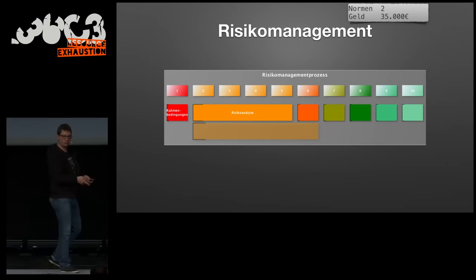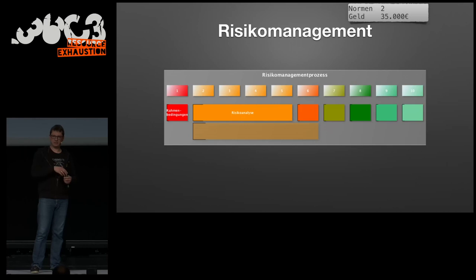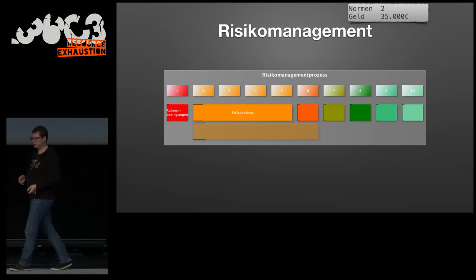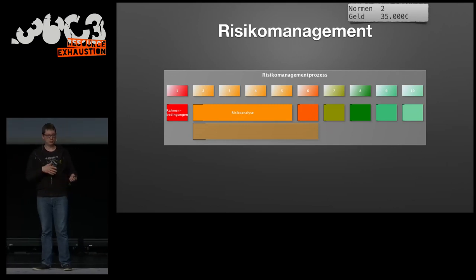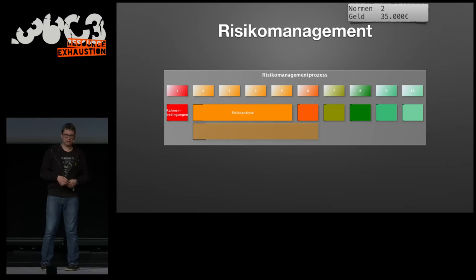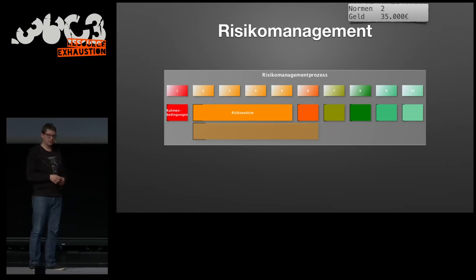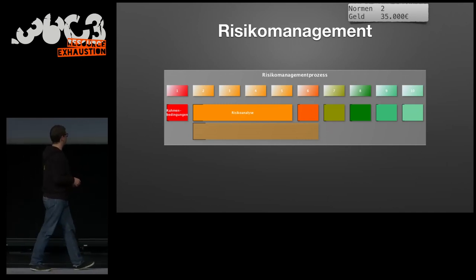From this situation, you have to go to risk. Risk is defined to be the combination of the probability of a hazardous situation happening and the resulting damage. These two values you can write down in a matrix and determine parts which are completely unacceptable, and other parts where you say it's not acceptable, but we'll leave it for now, because the use of the product, the advantages of the product, are more important. And that's what's written down here.